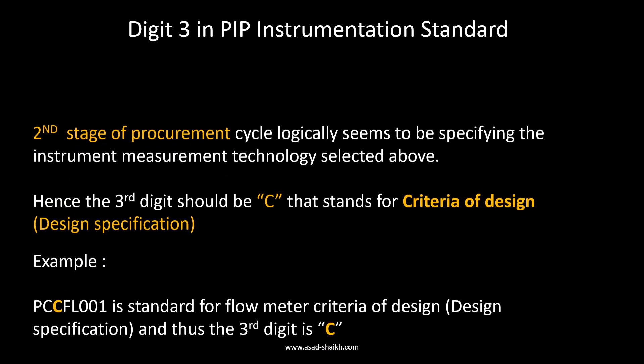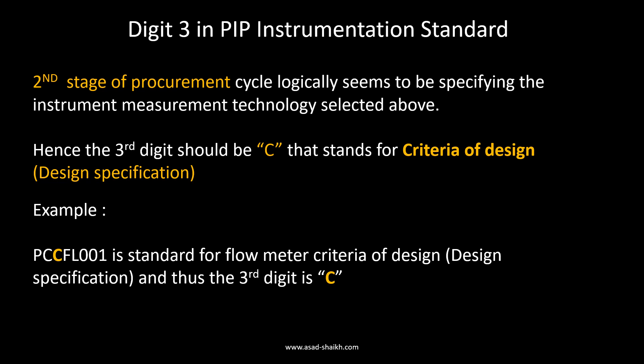Moving to other stages of the procurement cycle: the second stage is selecting the design or specifications. Suppose you determine that an orifice flow meter is your desired technology. You then need to specify details such as the type of tappings and their orientation. For this, the PIP standard is PCCFL001, where the third digit C stands for design specification, or what they refer to as criteria of design.